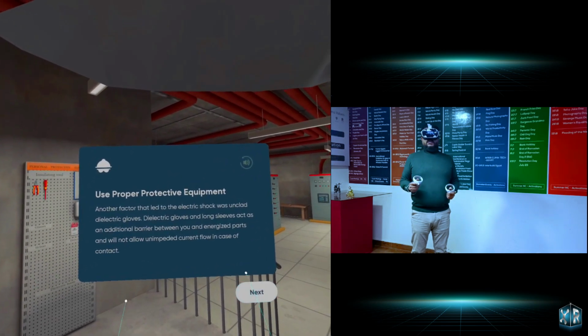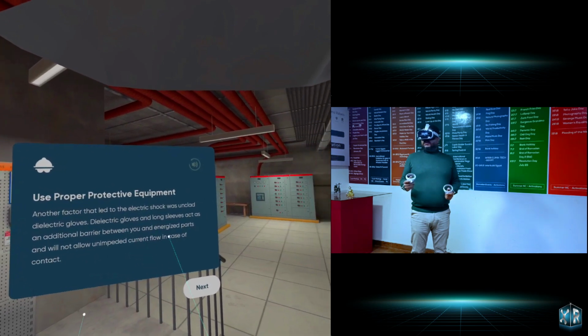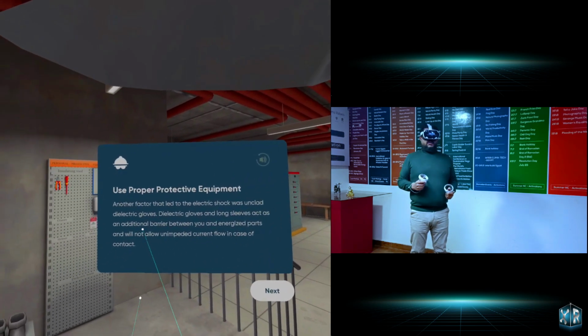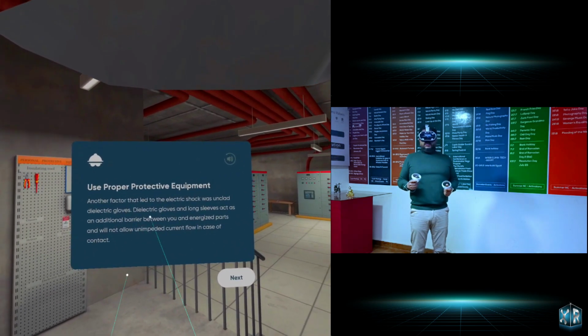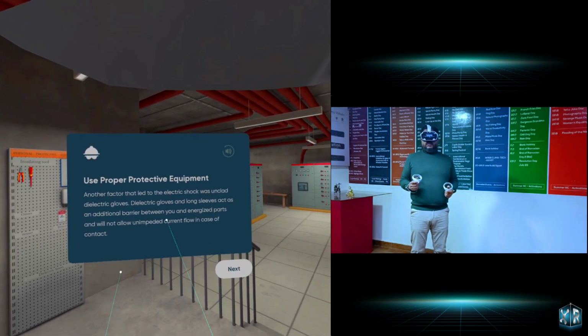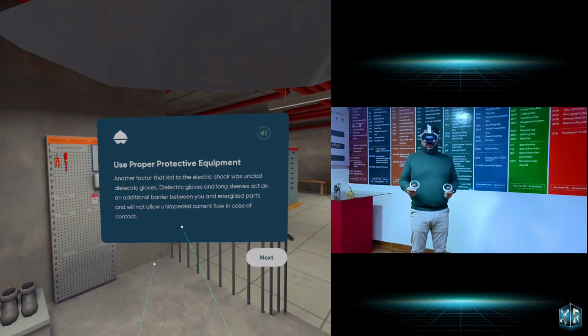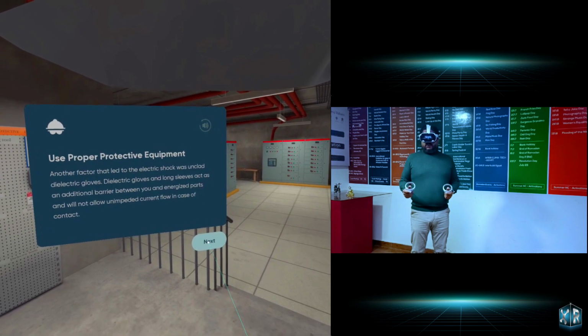Use proper protective equipment. Another factor that led to an electric shock was unclad dielectric gloves. Dielectric gloves and long sleeves act as an additional barrier between you and energized parts and will not allow unimpeded current flow in case of contact.